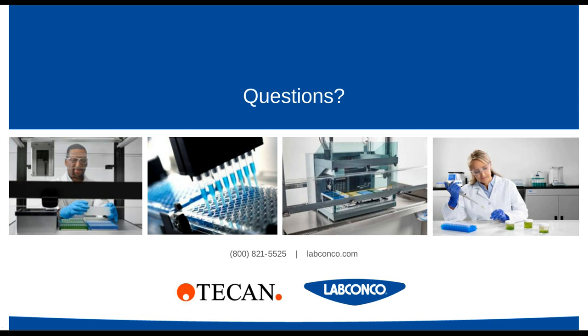Thank you, David. Our next question here is, what's the difference between BSC 2A and B? Good question. A Class II Biosafety Cabinet is overall a unit that provides personnel or user protection and also sample protection or product protection. Type A and Type B are subsets of the Class II Biosafety Cabinet family. A is very common on a regular traditional biosafety cabinet.